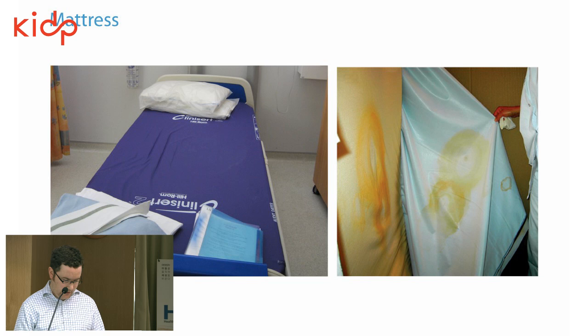We also looked at the mattresses. They consist of an outer waterproof layer and an inner foam core. The problem here is that needles or scalpels can make small holes in the waterproof cover and then fluid can get into the foam core and make it contaminated. And it's often impossible to tell just from the outside that the mattress is contaminated.